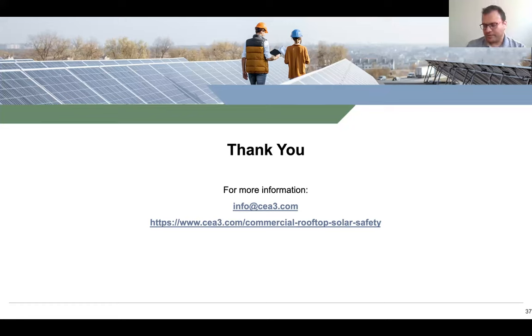That's a really good question. Usually the way I would recommend is, yeah, thermal camera points out to an issue. Sometimes you get the definite issue, but if it's a warranty issue, you can club thermal cameras with the IV curve tracing. For example, if you are a 4 megawatt site on the rooftop, do 100% of the IR testing through thermal cameras, depending on what you see from your results.